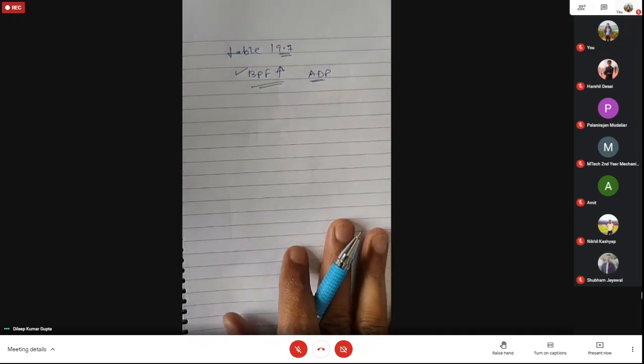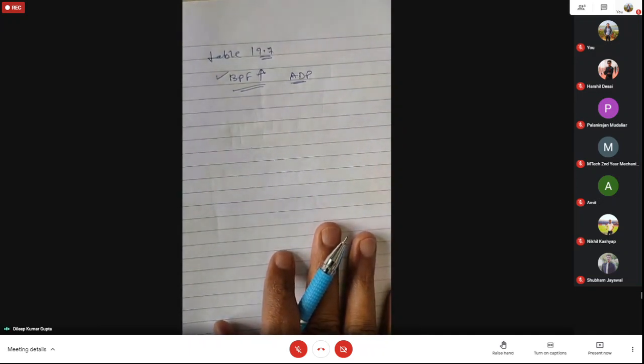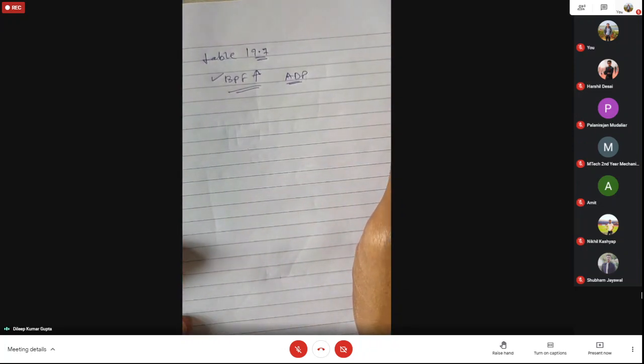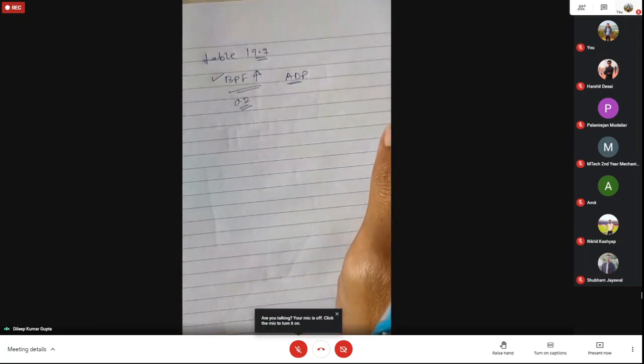Suppose you selected a coil and did the sizing for it. For example, you have fixed the air velocity, having 3 fins per centimeter or 6 fins per centimeter, and selected the depth of coil as 3 or 4. In this condition the bypass factor will be different, as given in table 19.7. From table 19.7, as per requirement, suppose we get the bypass factor value as 0.2.